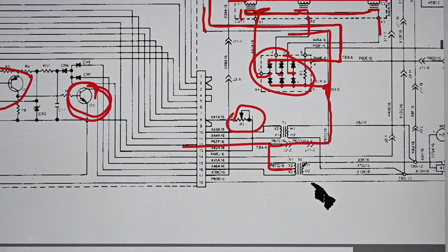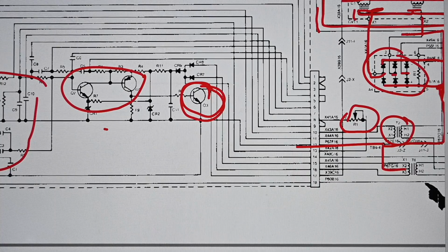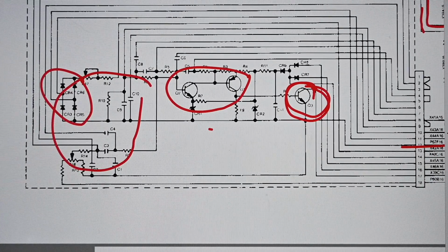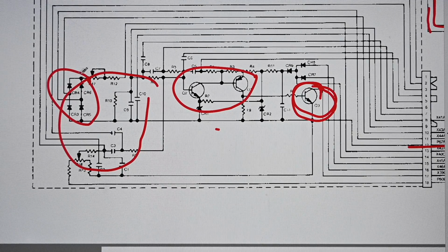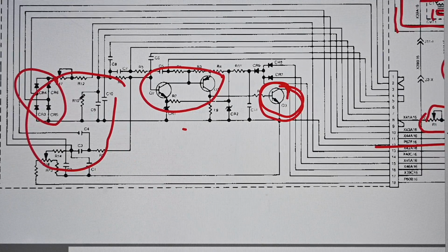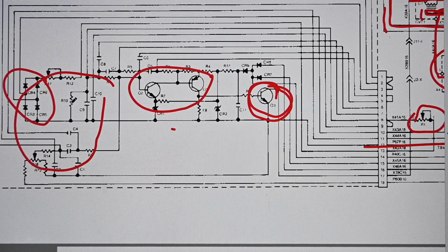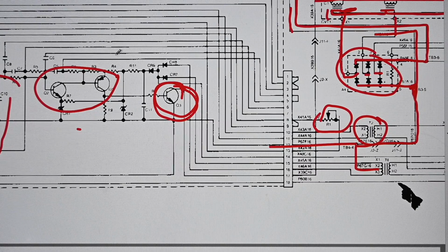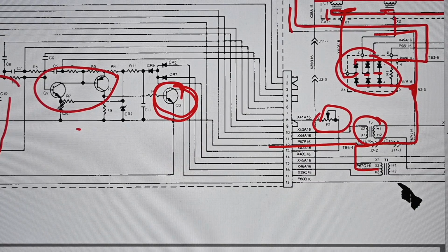This transformer is part of the sensing network, so we know it has 120 volts applied on the primary, and the secondary comes over here, ultimately going to this bridge rectifier. That feeds into some circuitry which again has to do with voltage sensing of the main generator's output voltage, and ultimately the reference voltage internal to the regulator.